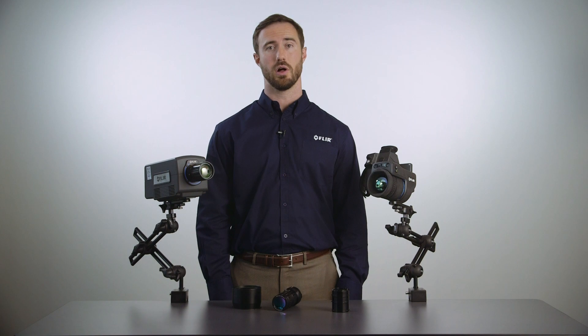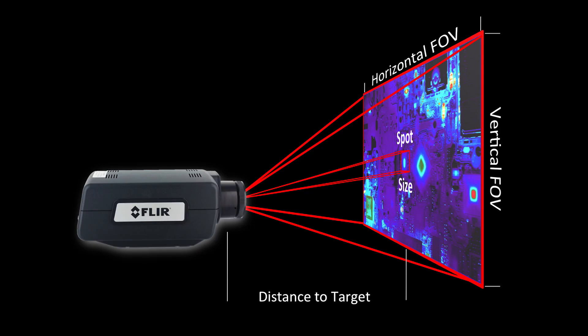Before we compare the field of view imagery from the cooled and uncooled cameras, let's review some field of view terminology. The horizontal field of view is what the camera sees at a given distance in the horizontal perspective, and the vertical field of view is what the camera sees in the vertical perspective. The spot size is what one detector pixel will see at a given distance. The fields of view and spot size will vary for a camera system and are dependent upon the lens in use and the distance to the target.